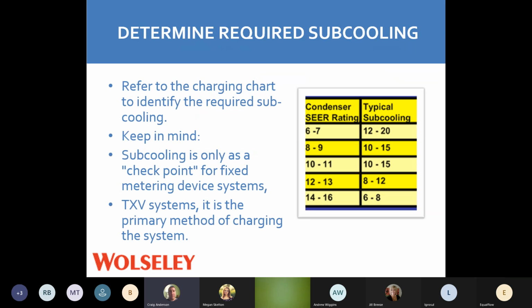So determining required subcooling. The unit's going to tell you typical subcooling, condenser SEER rating, sometimes depends on what kind of subcooling. So refer to your chart, whether it's in your book or it's on the side panel of the air conditioner or the heat pump that's out there. Subcooling is only a checkpoint for a fixed metering device system. TXV systems, it's the primary charge when we're doing a TX subcooling.